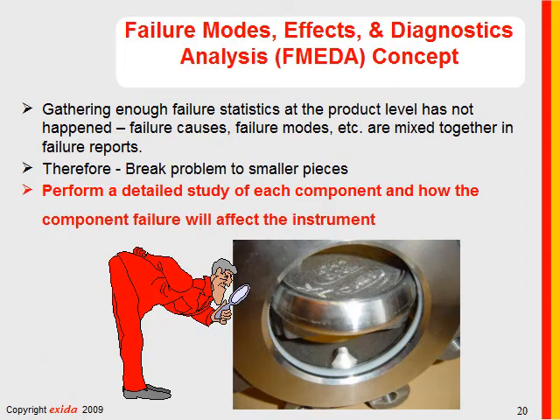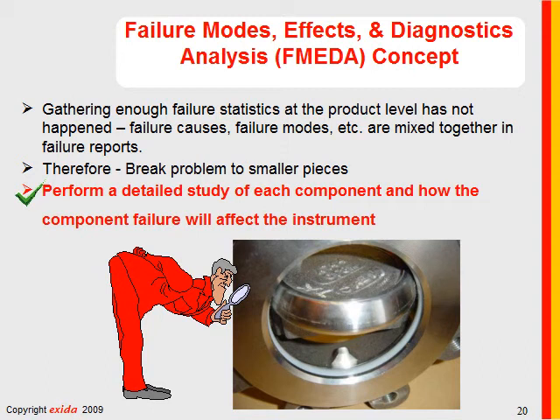FMEDA is a predictive failure concept that can be used on brand new designs based on design strength. It was derived because gathering sufficient failure statistics at the product level has not happened — neither manufacturers, end users, nor engineering companies do a good job gathering failure statistics, and when they do, the statistics aren't available until the product is obsolete. Therefore, we use failure statistics at the component level, breaking a design into its components and performing a detailed study of how each component affects the instrument.